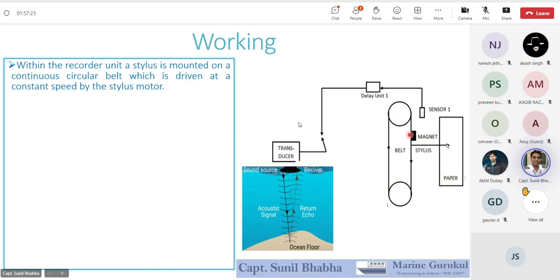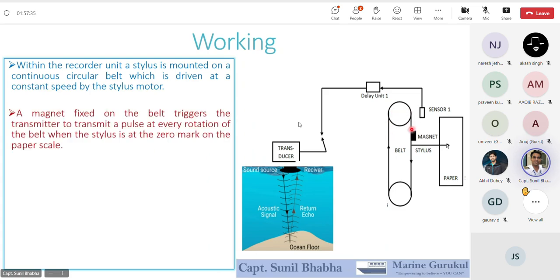Now this belt is driven at a constant speed by a stylus motor. There is a motor fitted and that motor drives this belt with a constant speed. Also, if you look here, there is a magnet which is fitted on the belt. This magnet triggers the transmitter to transmit a pulse at every rotation of the belt. You see when the belt is rotating and when the stylus reaches the zero mark, somewhere here, this magnet sends a signal to this particular sensor. The sensor catches this magnet and this sensor then sends a signal to the transmitter which is there in the transducer and it transmits the echo towards the ocean floor, towards the seabed.